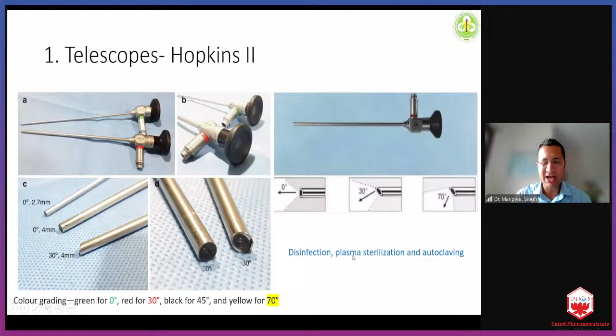These can be disinfected, plasma sterilized, or autoclaved. This image will tell you how delicate this structure is. I have broken one, and that costs around 2 lakh for Karl Storz. Then I got to know that there are rod lenses inside, with spacer lens arrangements, and this is the field of view we get from the telescope. The telescope converges the light at the eyepiece, from where the camera picks it up, and it has another end where the light post is. Here the light pipe attaches, I'll be showing that. And this is how the tip of the telescope looks.